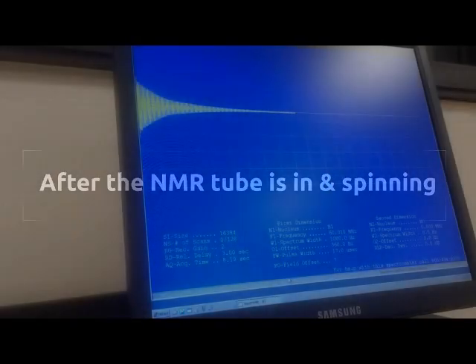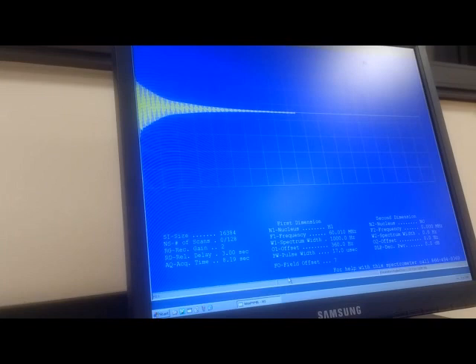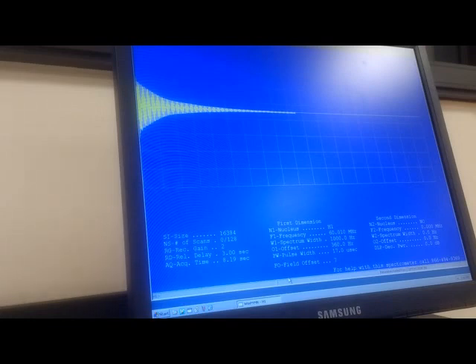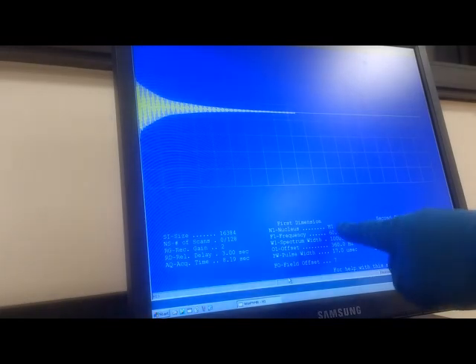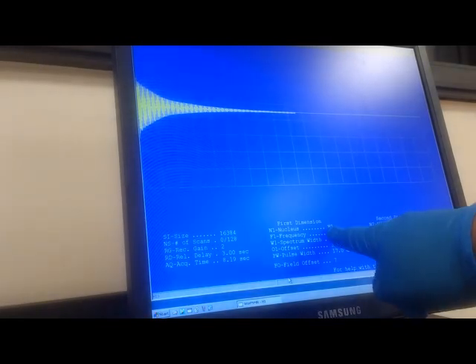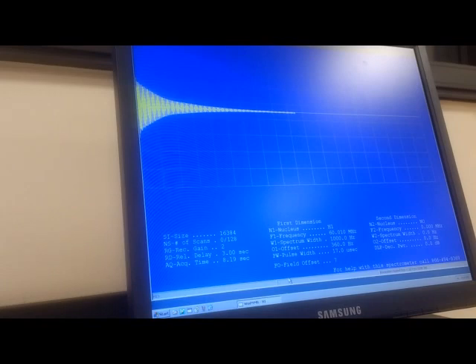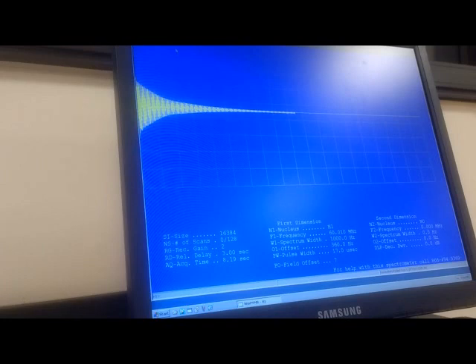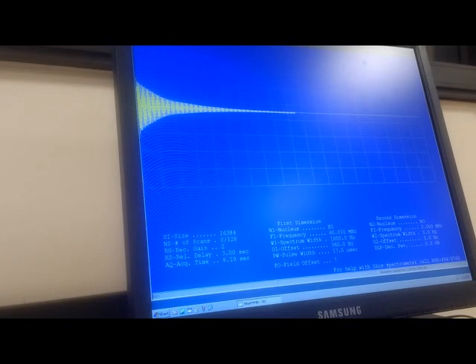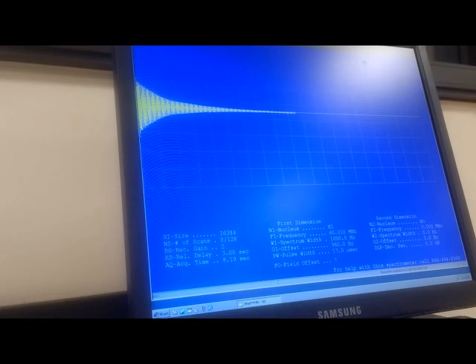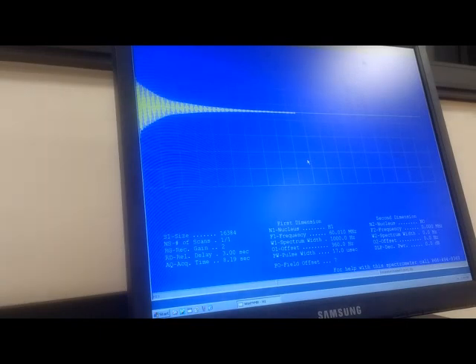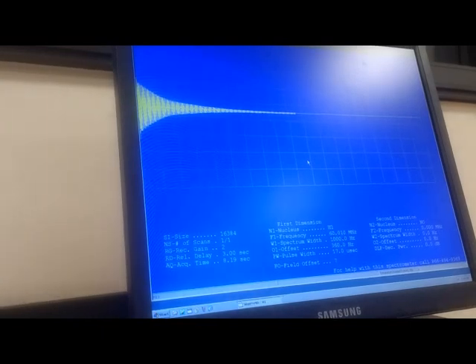Once your NMR sample tube is in the machine, the next thing you want to do is to shim the magnet. But before that you will actually want to make sure that the nucleus that's chosen for the experiment is proton. And you can see that right there it says H1. That's the right nucleus. We want to do a proton experiment. Now if that says something different, sometimes it may say C13 because either for a class or research purposes we may use C13 NMR. You will want to go on the top where it says change nucleus and type in H1 and hit enter. That will change the nucleus to proton.